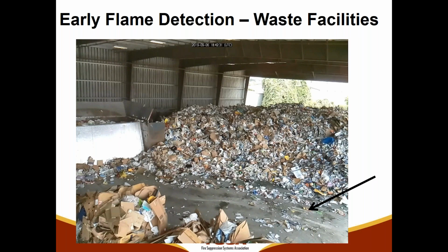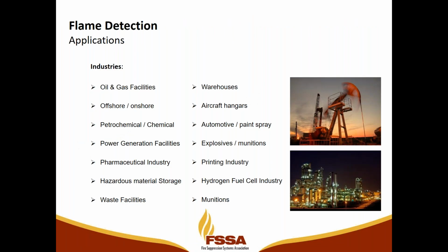You can see just there, down in the bottom right-hand corner, a small flame ember jumped into the screen, caught a piece of paper on fire, and was detected very quickly by the triple IR detector. So we had proof of what the event was to show the end user. So, standard applications for radiant energy detectors. I won't go into these, primarily industrial.